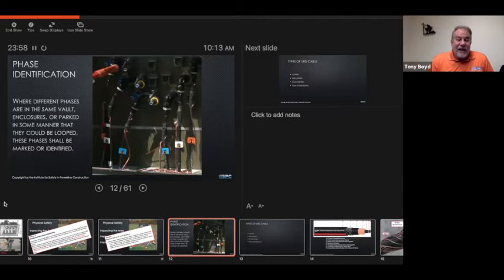Phase identification. Where different phases are in the same vault or transformer or in the same vicinity, they shall be identified. I actually had several crews that worked for me years ago, and all they did was go around to old subdivisions that were installed back in the 70s and 80s that were not identified, and their task was to identify cables, and it was a very difficult task to do. Where different phases are in the same vault enclosure or are parked in some manner that could be looped, these phases shall be marked or identified.